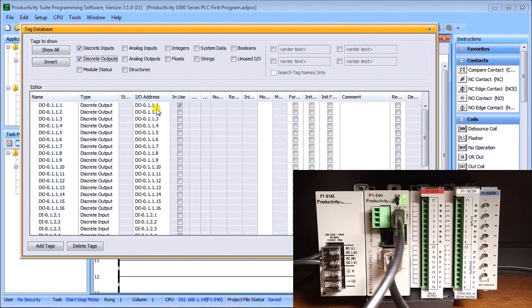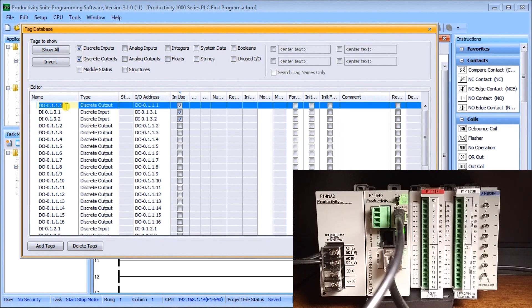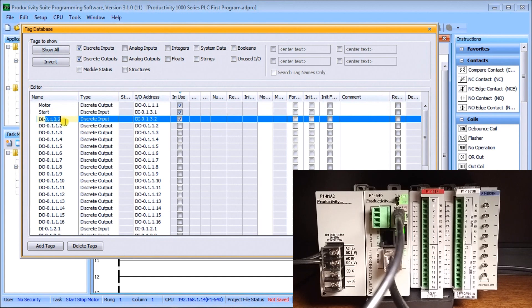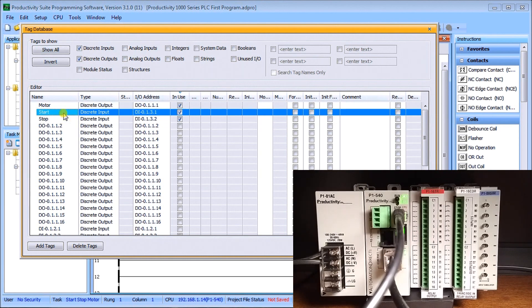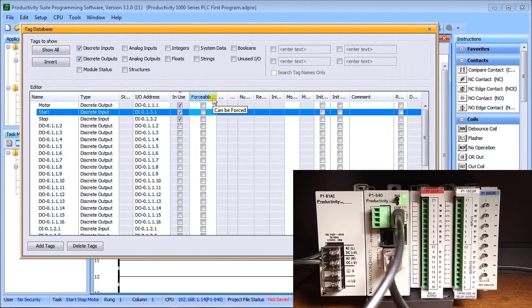We have our I/O address and name columns. We'll sort by 'In Use' — clicking the column header sorts it descending or ascending. Now we can see our output and our two inputs. We'll double-click the name field and call the output 'Motor,' the first input 'Start,' and the second 'Stop.' We can also drag over the 'Forceable' column to see which contacts can be forced.